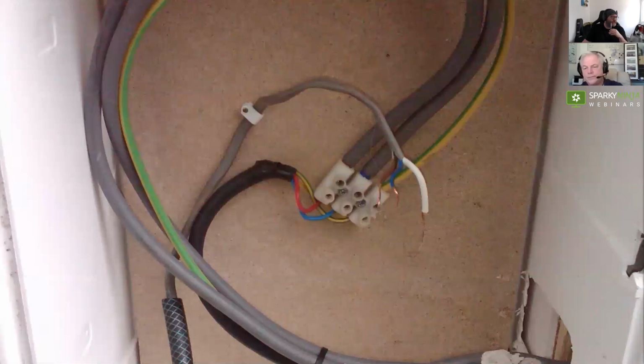Mickey Molly asks, what would you code a type AC RCD that protects DC components? Well, it depends really on the behavior of the DC components, in my view. If the DC components are potentially going to have leakage current that is DC in nature, and if it's likely to impact the effectiveness of the RCD, we might, trying not to say we will, but we might eventually in the next 5 or so years be tipping into the territory where a lot of AC RCDs will be considered as dangerous if the equipment connected to them makes them defunct.